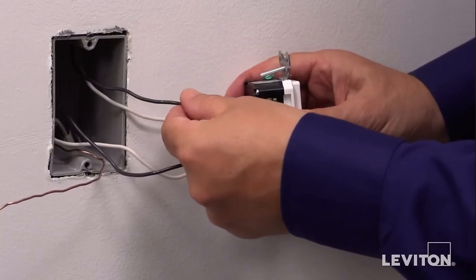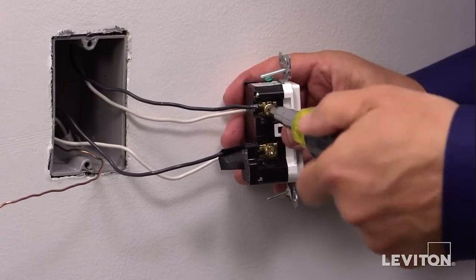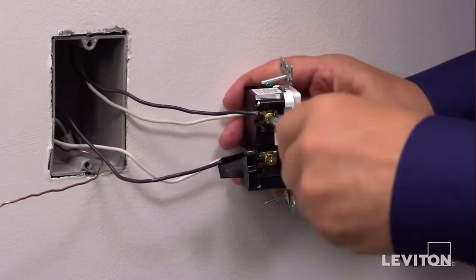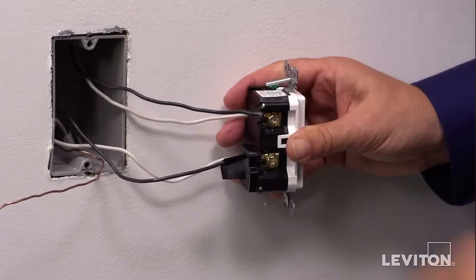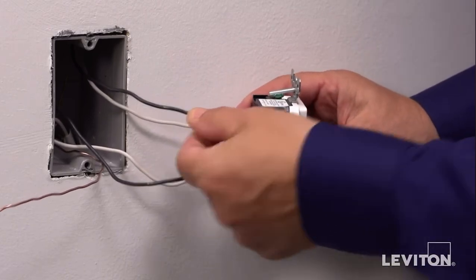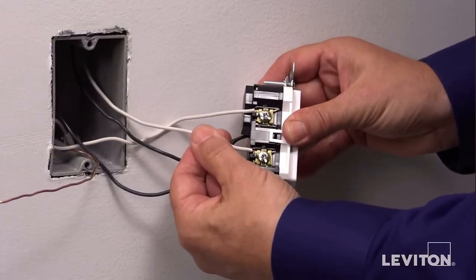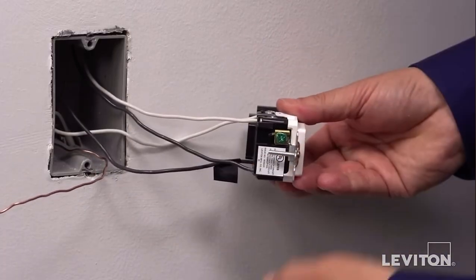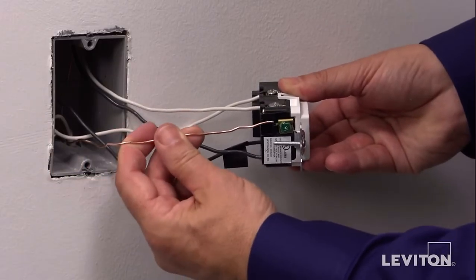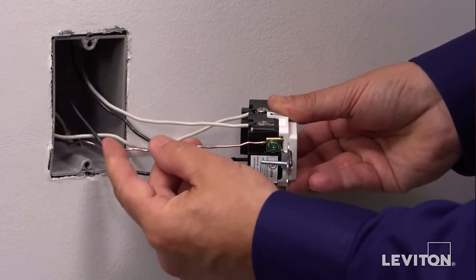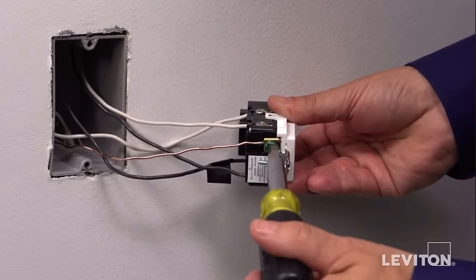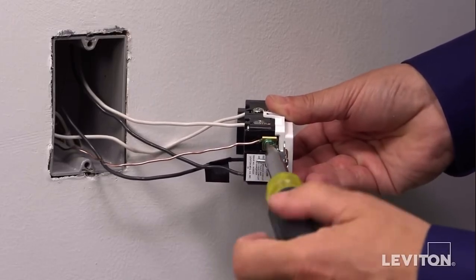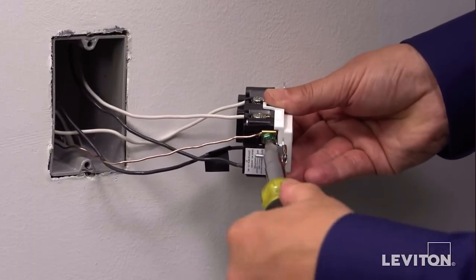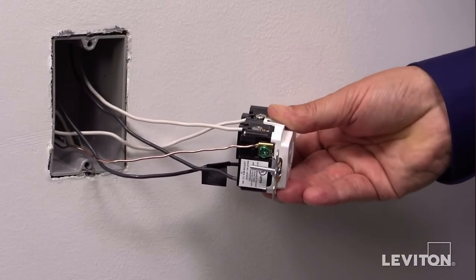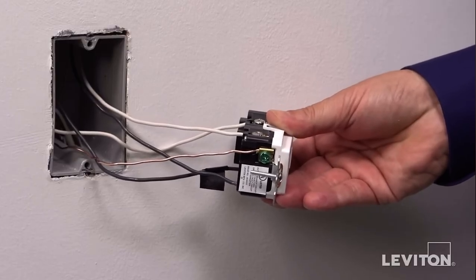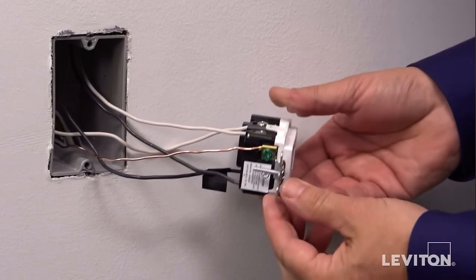and the black load wire connects to the hot brass terminal. Use a screwdriver and rotate the terminal screw clockwise to tighten the conductor portion under the clamp. Give a tug afterwards to assure the wire is securely terminated. The last step is to terminate the ground wire, which is the green or bare copper wire. Ground screws are always hexagonal in shape and colored green. We will follow the same procedure as with the other terminals. Use a screwdriver and rotate the terminal screw clockwise to tighten the conductor portion under the clamp. Give a tug afterwards to assure the wire is securely terminated.